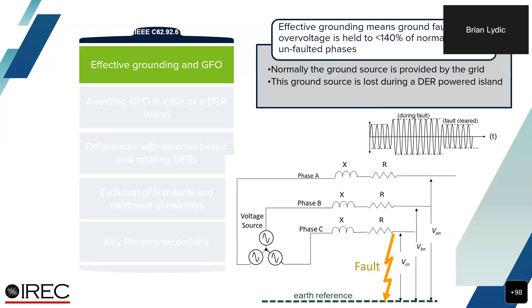Effective grounding really means that we're concerned that when there's a ground fault, you get an overvoltage on the unfaulted phases. That's what this picture depicts, from the time the fault occurs until it's cleared. You can see that overvoltage, and systems are designed to withstand that. But we use effective grounding to keep it down to that 1.4 that you see in the note there.